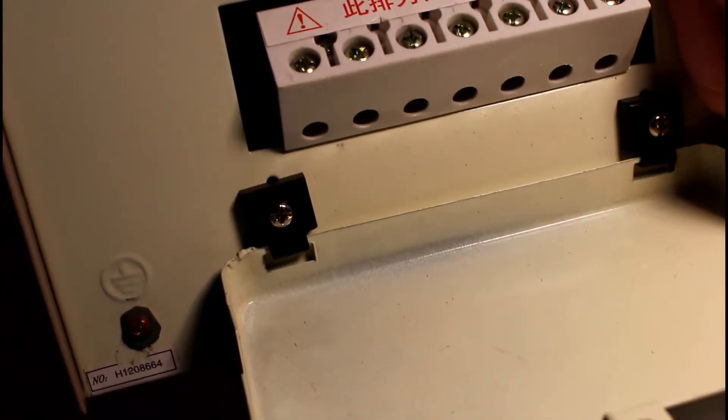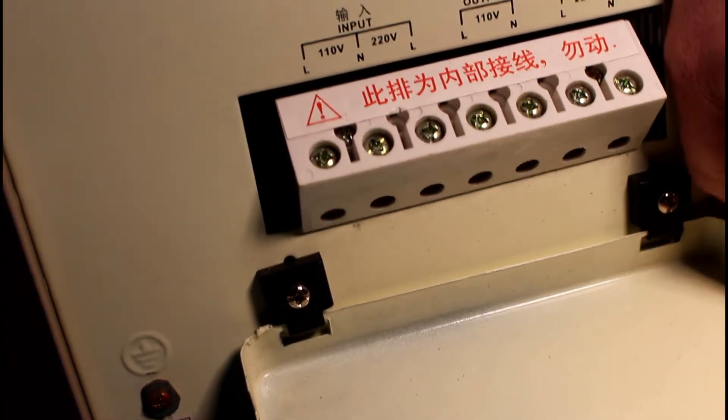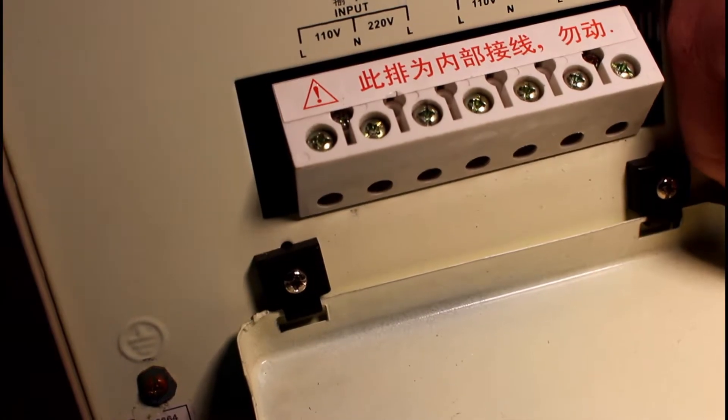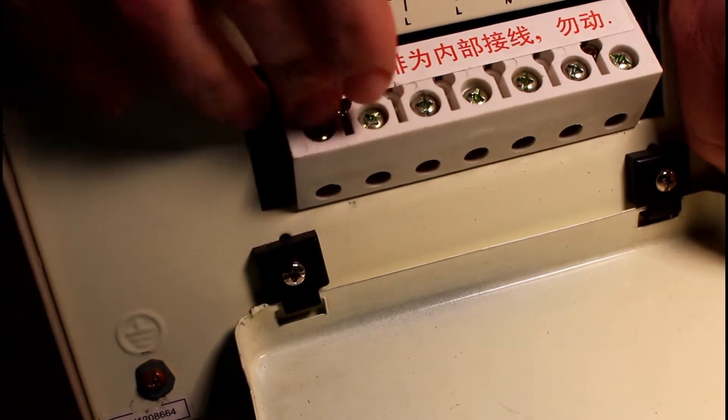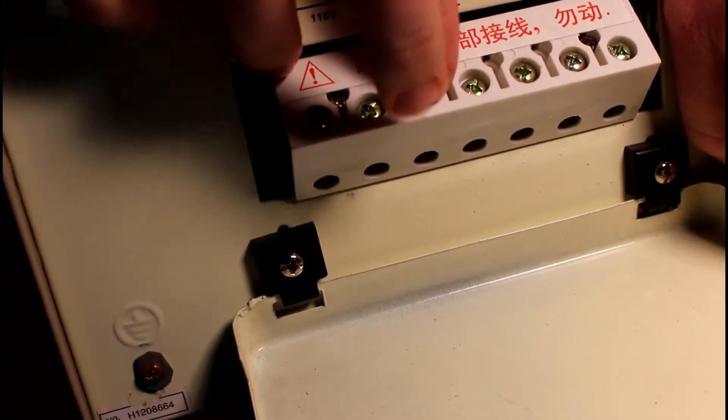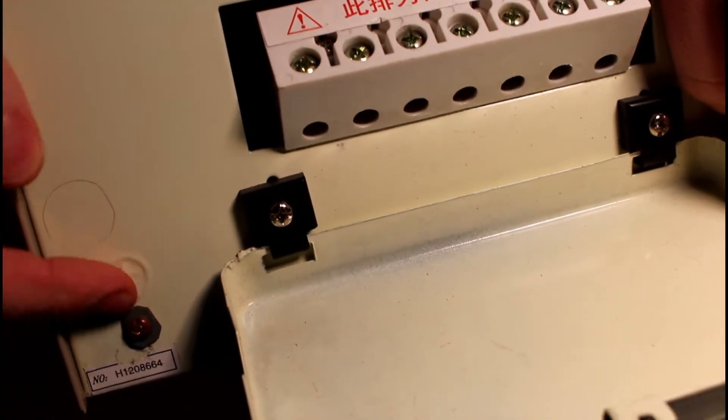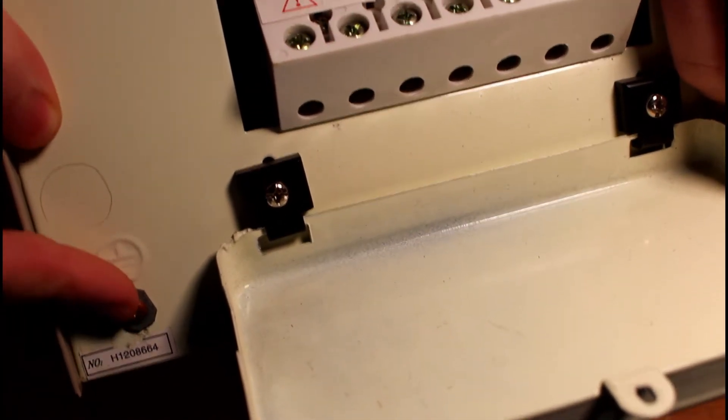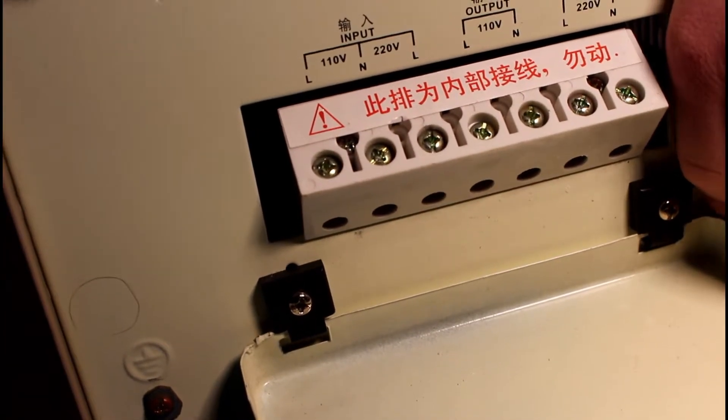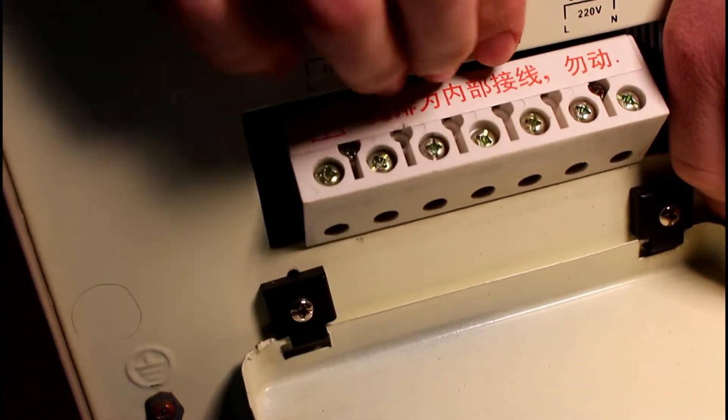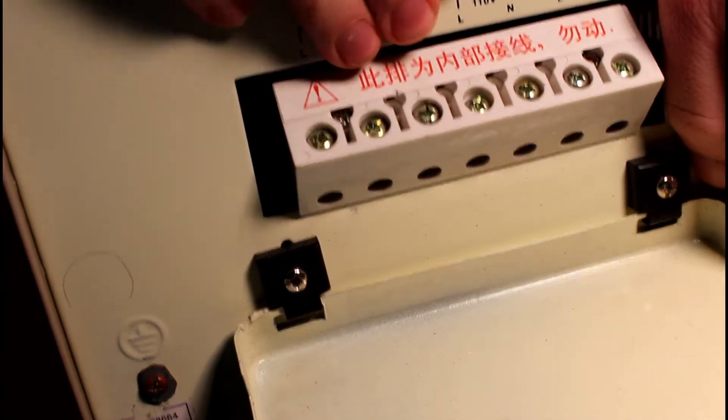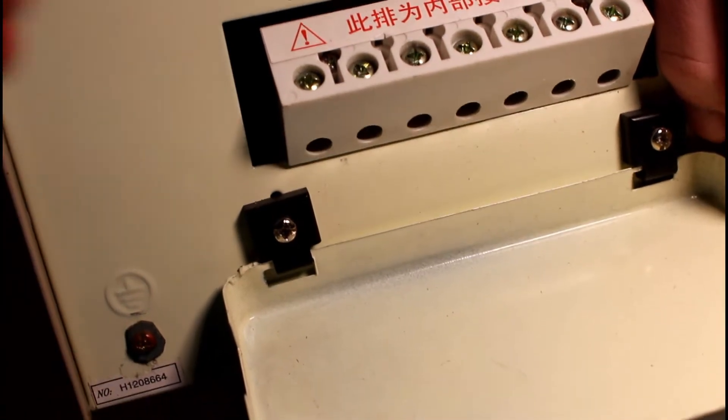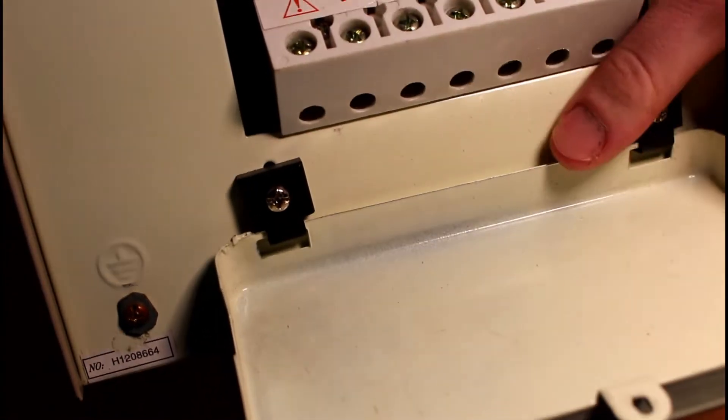I should just point out real quick that if you are actually going to wire up this transformer or one like it for use, then there's a third connection that you need to make in addition to the 110 and neutral or the red 110 and black 110. And that's the ground connection, which goes to the chassis over here. The ground connection is just there in case there's an electrical or mechanical failure inside of the transformer that causes one of the hot lines to short out to the chassis. Then you want that to short out through the ground and trip the circuit breaker instead of shorting out through your heart and killing you.